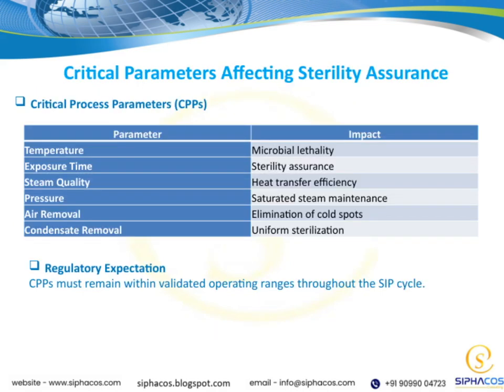When we talk about regulatory expectations, it all comes down to keeping critical process parameters, or CPPs, within validated limits throughout the sterilization cycle. These parameters each play a key role in ensuring sterility. Temperature controls microbial kill. Exposure time guarantees the process is long enough. Steam quality affects how well heat transfers.